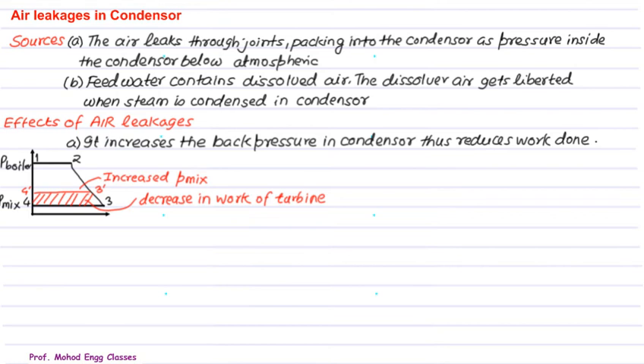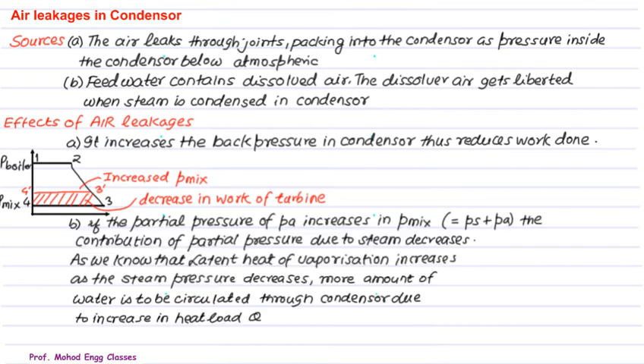Hence you have to always reduce the air leak in the condenser. If the partial pressure P-a increases in P-mix, which is equal to P-s plus P-a, partial pressure of steam plus partial pressure of air, for the same value of P-mix, if P-a increases then the value of P-s will decrease.